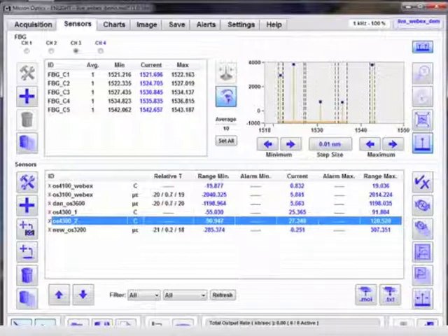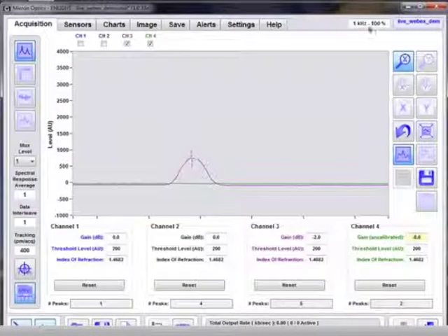The new question is, can I lower my SM130 sample rate down from 1 kilohertz? And the answer to that is yes. If we go back to the acquisitions tab, you'll notice here on the upper right of all of our views, we see the acquisition rate here at 1 kilohertz and the available buffer percentage. So here 100% means that we have 100% of our buffer available and that none of it has been used up by our Enlight client falling behind our host instrument.